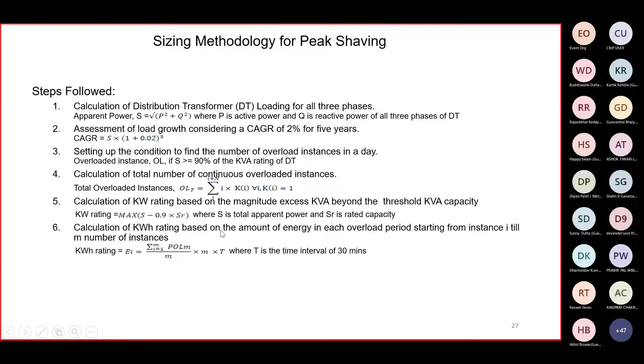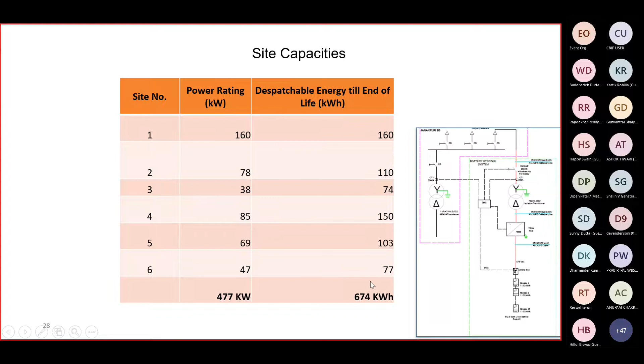There were 6 sites, 6 distribution transformers, and at each site the power rating and kilowatt-hour requirement varied because of the load profile and load duration curve of these transformers. The cumulative capacity we have deployed is 477 kilowatt and 674 kilowatt-hour, with a C-rate of 0.5C at all sites.